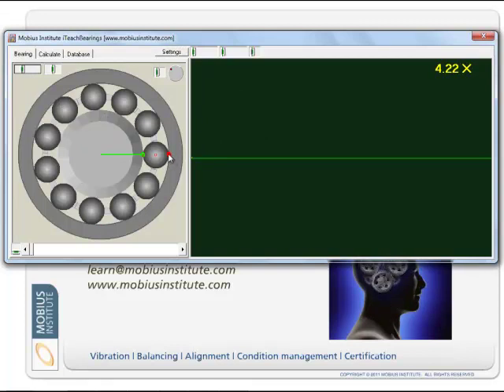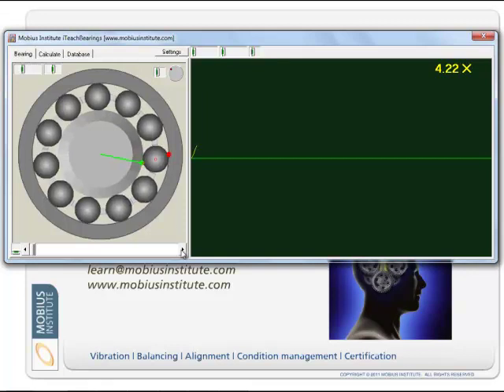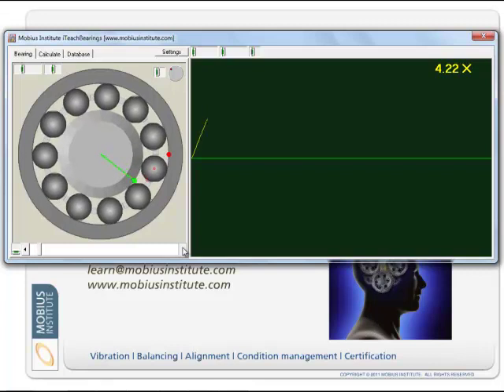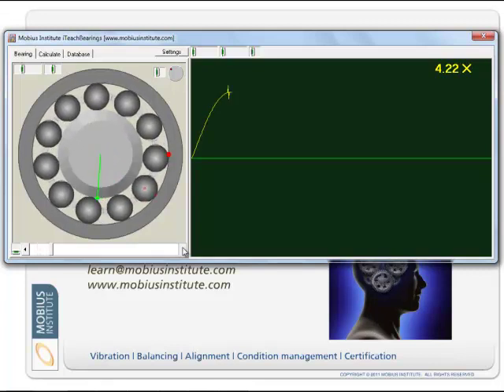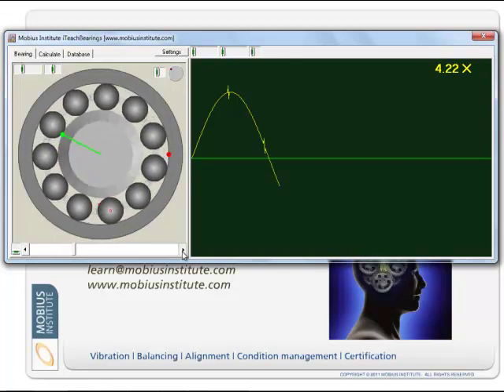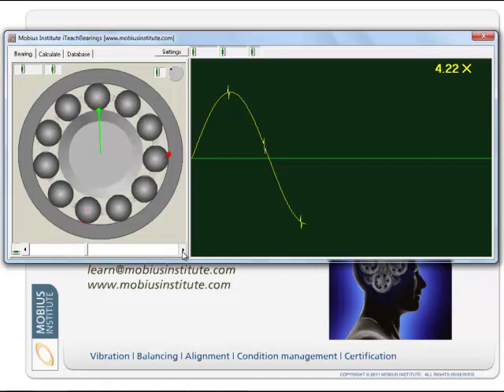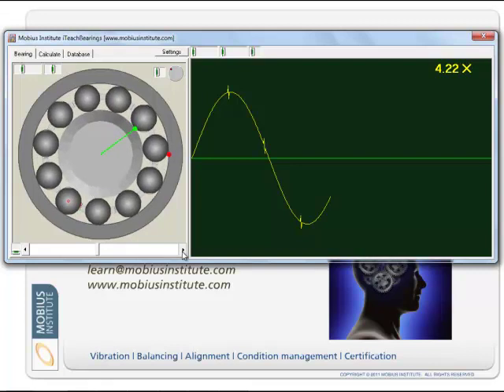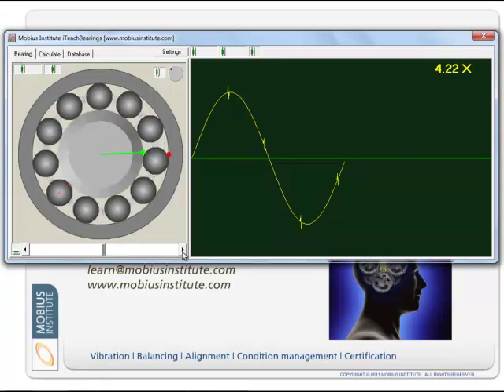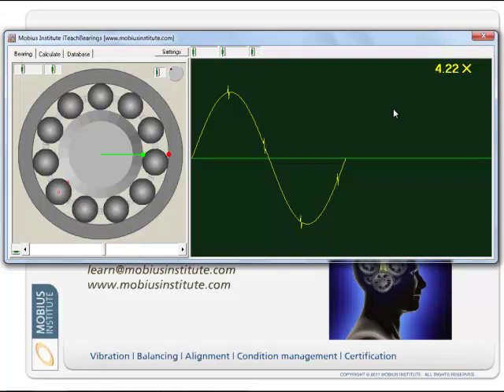In this mode, the shaft has stopped and we've put this green reference mark. If I'm interested in vibration related to a fault on the outer race, I can slowly rotate the shaft here, and we can see that at this point we just started with one of the rollers touching. We scroll it and we scroll it, and we see one impact — then two, three, four — and if we complete the rotation, that green line needs to be horizontal, we've got four and a bit.